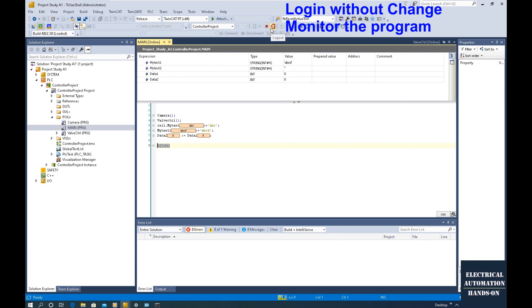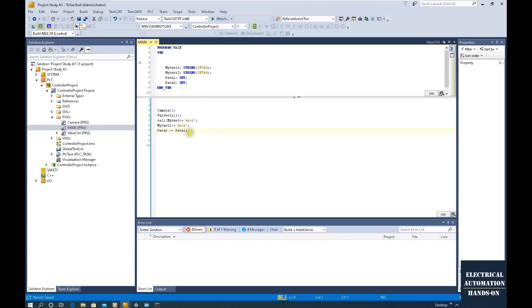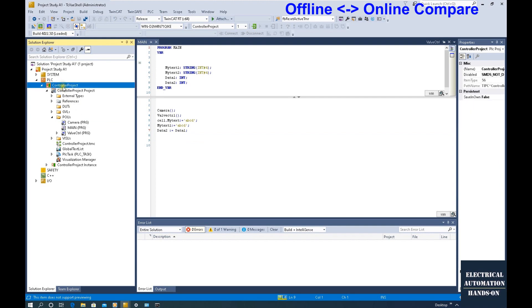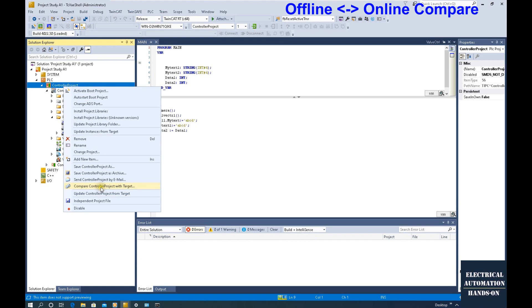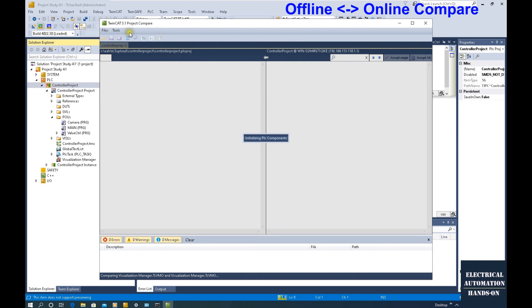Now I'm going to show how to compare. First let me logout. I assume I changed one code — for example, I change this variable to ABCD and save it. Now I'm demonstrating comparing this offline modified project with the online project running inside the remote PLC. A compare window will pop up. This allows us to compare our offline with the online PLC controller. The left side is offline, the right side is the remote PLC controller. The bold text shows the changes. Let's expand it to show the detail.